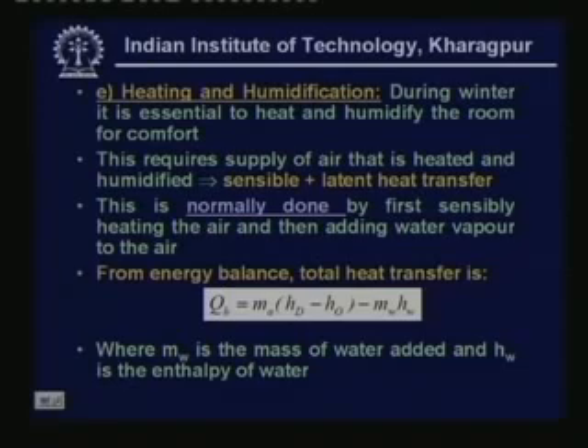Now, let us look at another process called the heating and humidification process. During winter, it is essential to heat and humidify the room for comfort. This is basically required in cold countries for winter air conditioning systems. So, you have to heat and humidify the air, that means you have to increase its temperature and also increase its moisture content. This requires supply of air that is heated and humidified. That means both sensible and latent heat transfers are involved again. This is normally done by first sensibly heating the air and then adding water vapor to the air.